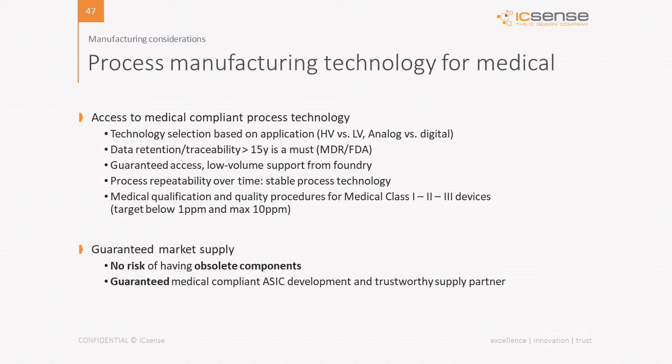Next to the design considerations I would like to share with you, there's also an important one related to the process manufacturing and the technology for medical devices. Access to medical compliant process technology is key for your medical development. So you need to choose a technology that is suitable for medical applications. In most cases, we select a technology based on the application.